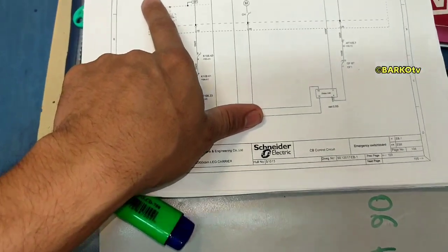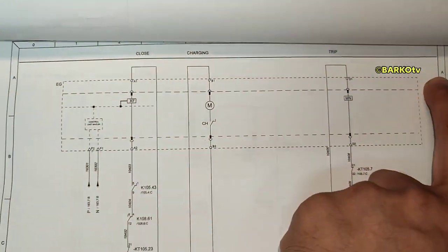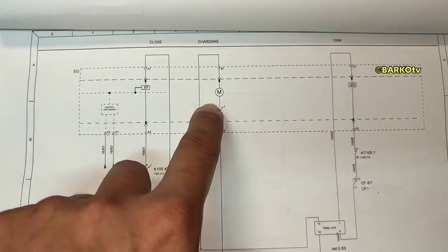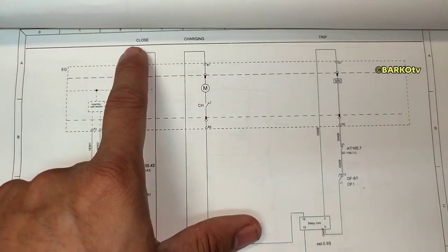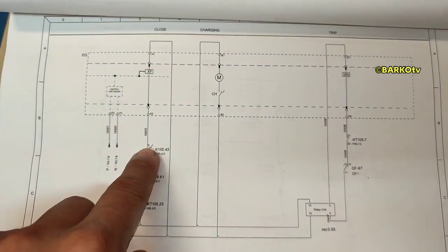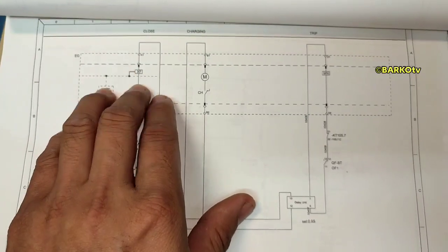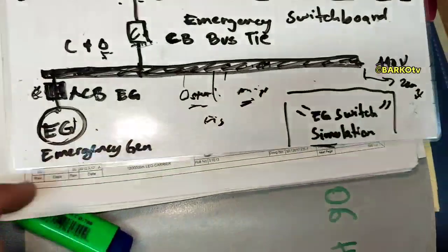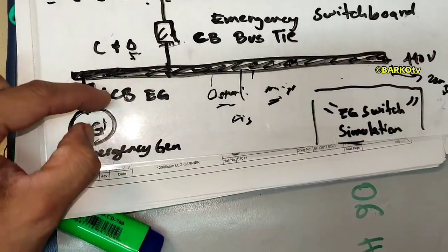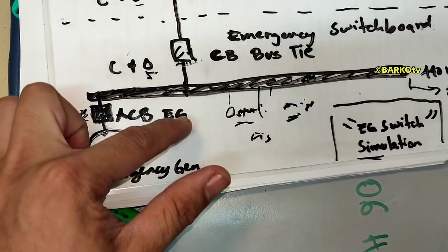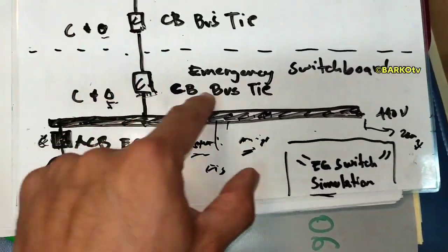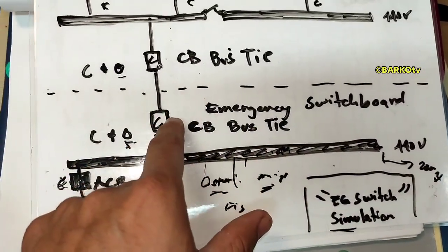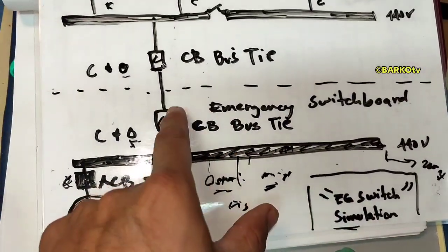The emergency generator running command is issued after the delay. This is the breaker for the emergency generator — there is a motor that charges the spring mechanism. This is the trip coil for open and this is for close. After the delay this will close the emergency ACB breaker, and the emergency generator will supply the switchboard. The simulation switch open and test commands open the bus tie breaker, the emergency generator runs, the ACB closes, and 440V is supplied.